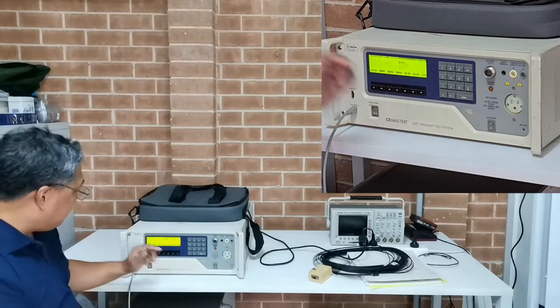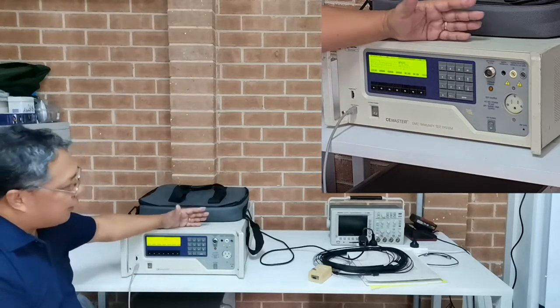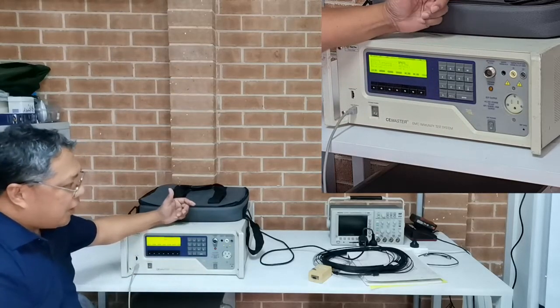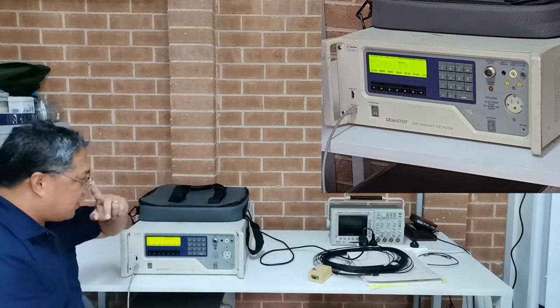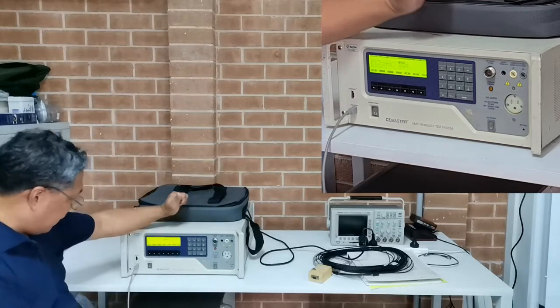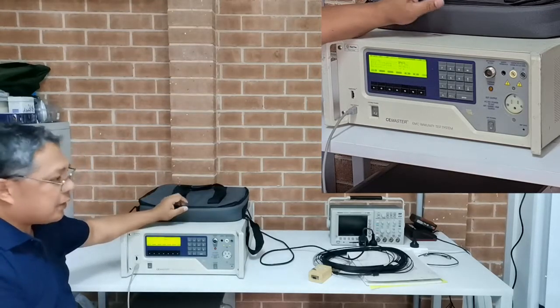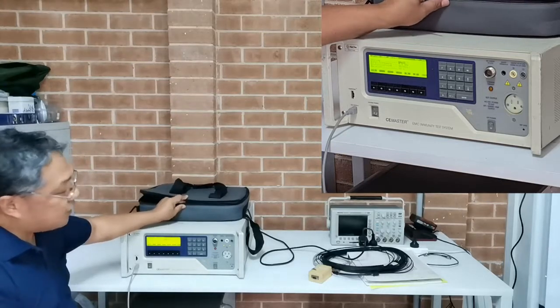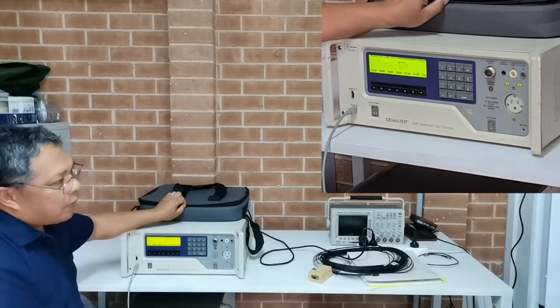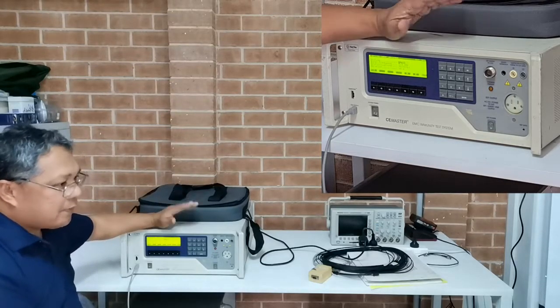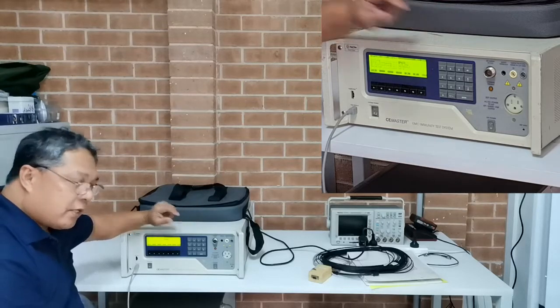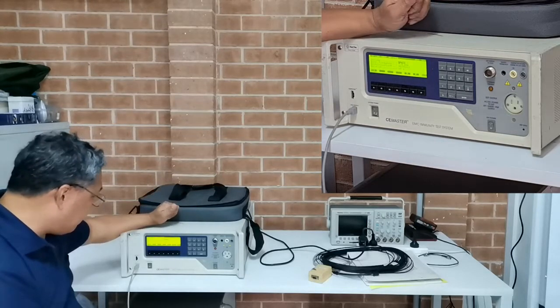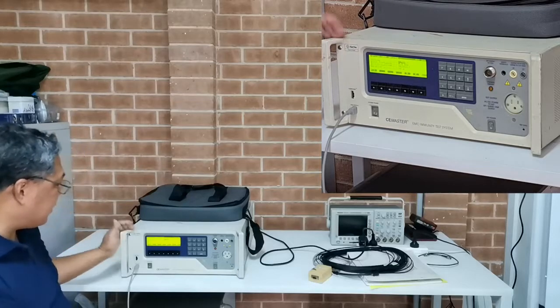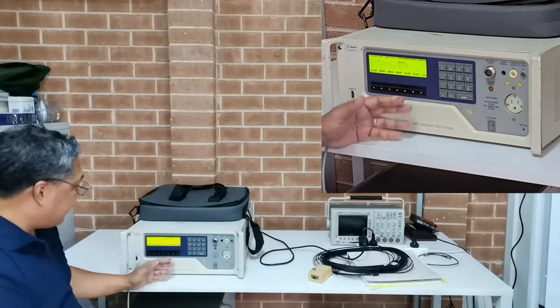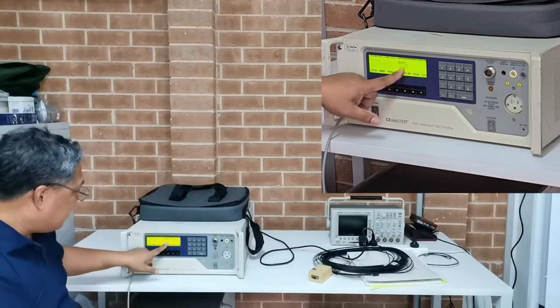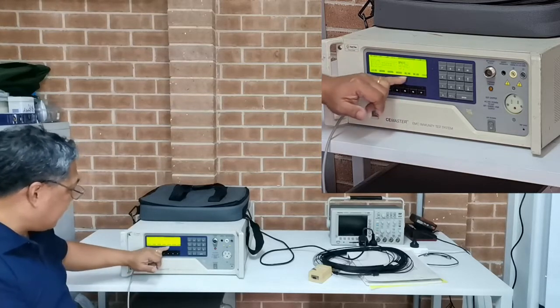With this one, the burst frequency is only 5 kHz, unlike the KeyTek EMC Pro Plus, which has a 100 kHz burst frequency. But that's not a problem. It's an option. The standard doesn't really require it. There's some particular standard that requires a 100 kHz burst frequency, but most of the standards only require 5 kHz. So we can definitely use this 5 kHz burst frequency.